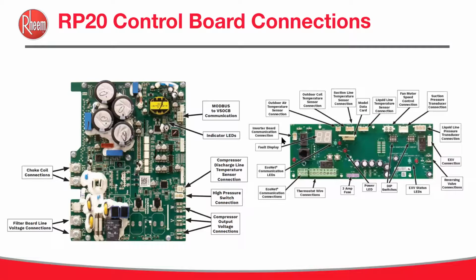As well, there's the operation of the electronic expansion valve. So we have a green light. If it's solid green, it means the electronic expansion valve is fully open. If it's flashing green, it means it's opening. We have a red. Solid red means the electronic expansion valve is closed. If it's flashing red, it means it is in the process of closing. So without even having tools, you get a lot of information.